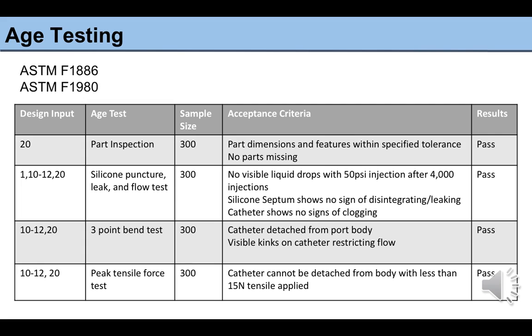In the DV protocol, we looked at part inspection, looking at the part dimensions and features to make sure that they're not out of tolerance and no parts are missing. We looked at the silicone puncture, leak, and flow tests for the silicone septum at the top of the port to make sure that no liquid drops are visible, the 50 psi injection and 4,000 injections, and that the silicone septum showed no signs of disintegrating or leaking, and the catheter showed no signs of clogging.